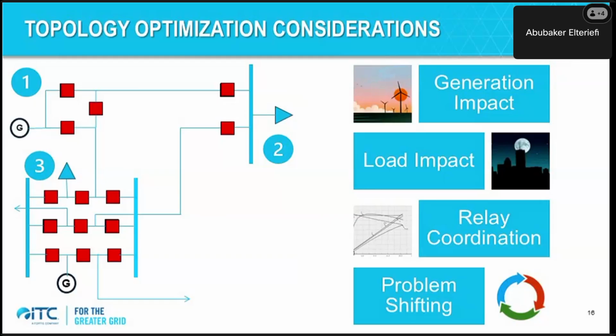If you open one of the breakers there, you change the contingency in this case. So if you lose the line between station 1 and station 3, instead of that being a contingency that's causing an issue, you would drop the generator. You'd have to coordinate with the generator, but that contingency is no longer a concern.